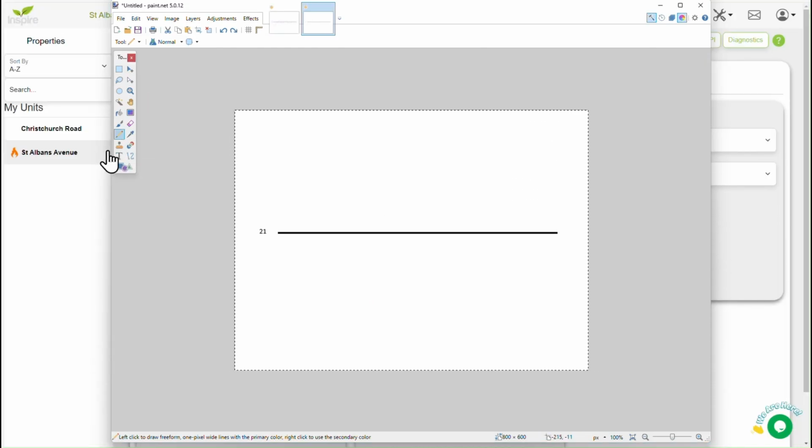So just to give you a demonstration of how optimized temperature control works, if we move back to here, what would happen is we wouldn't have those plus or minus lines, because it doesn't work like that, but we would have, let's imagine, a line down here. I'll put it in blue. And then the heating switches on. So again, it warms up in a similar way, but this time when it hits that line, which is calculated based on the temperature, how quickly the property warms up, the current temperature in the property, and various other factors, it will switch the heating off at this line.